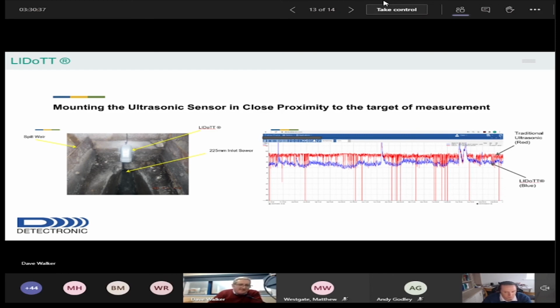We can pick up the diurnal patterns, and the information we can gain from that can help with the forecasting, the algorithms, the fuzzy logic and all that data analysis that has to go into post-processing. So the closer we can mount our ultrasonic level sensor to the target of measurement, keeping it focused, getting that energy back, is the way to go. You can see that in the comparison of the data on the right-hand side. The red data is the traditional ultrasonic level sensor with that spiking, as we saw earlier, that noise. If you've got that red data, you've got to try and pre-process it and get rid of all that background noise that's distracting from the true reading.